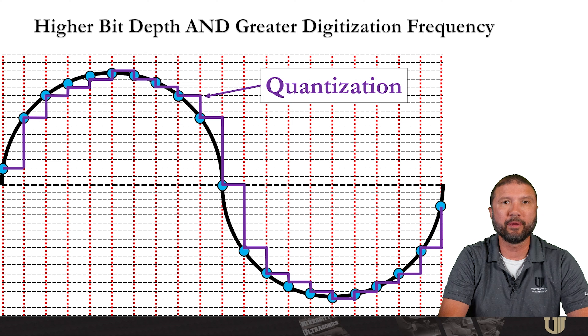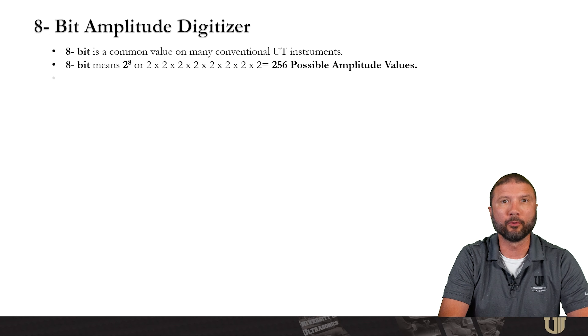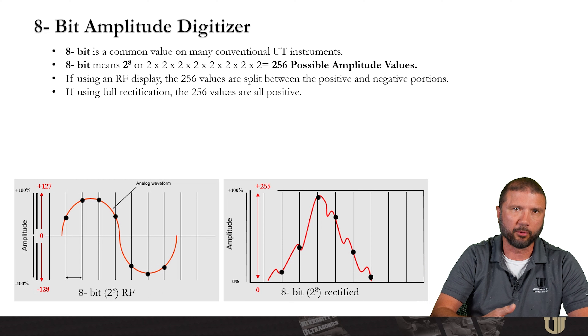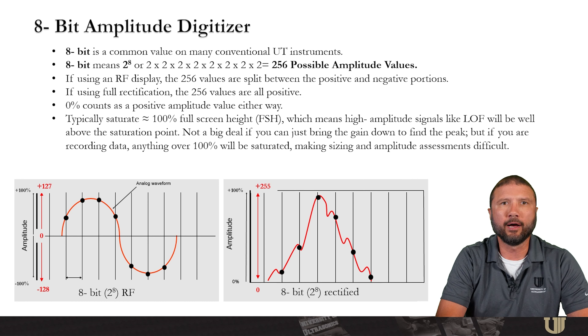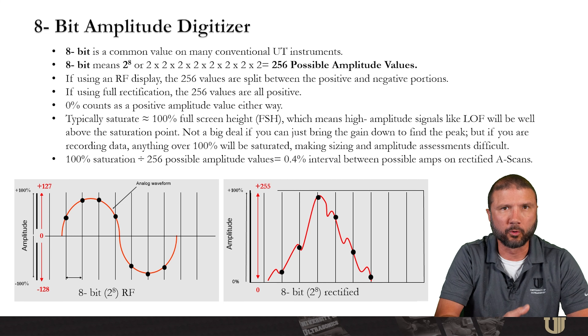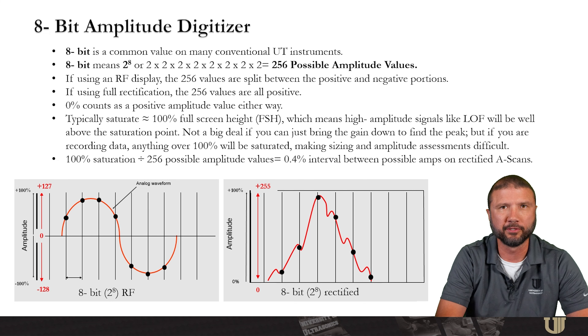Now we're going to discuss some of the common amplitude digitizer bit depths in the industry. 8-bit is a common value on many conventional UT instruments. 8-bit means 2 to the 8th power, or 256 possible amplitude values. If you use an RF display, the values are split between the positive and negative portions; if using full rectification, all those values are positive, and zero counts as a positive amplitude either way. These typically saturate at 100% full screen, meaning high amplitude signals like lack of fusion will be well above the saturation point — not a big deal if you just turn the gain down to find the peak, but if you're recording data, anything over 100% will be saturated, making sizing and amplitude assessments difficult. 100% saturation divided by 256 possible amplitude values gives 0.4% interval between possible amplitude values on a rectified A-scan.